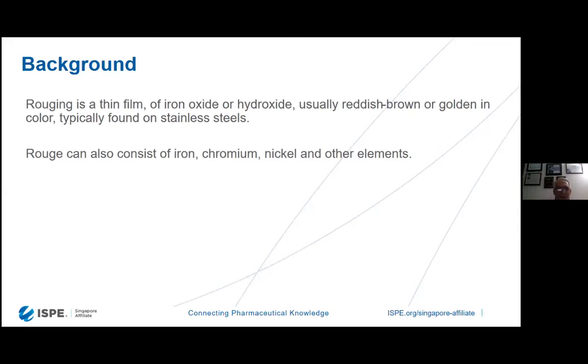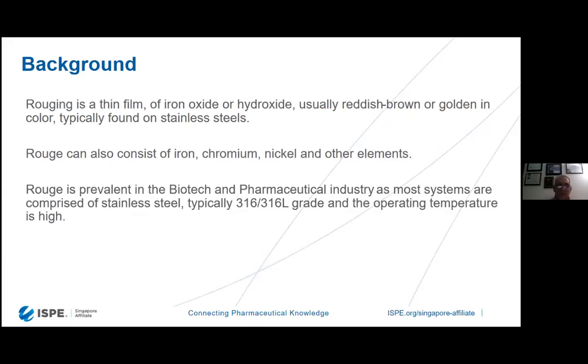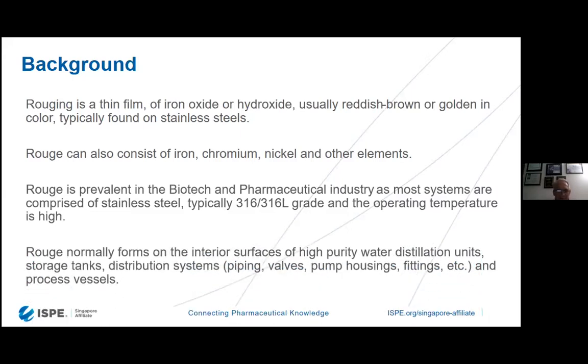Approximately 75% of all the stainless steel that's used today in the industry is actually recycled stainless steel, and tungsten is used during recycling. When that happens, it means that there are other oxides that are formulated that cause Rouge also, not just iron. Iron is the most prevalent because it's over 60% of what's made up in stainless steel. Rouge is prevalent in the biotech and pharmaceutical industries because we use a tremendous amount of 316 and 316L stainless steel and operate typically at temperatures that are very high. Not all the time. There are many ambient systems out there. They still Rouge also, but not as flagrantly as high temperatures.